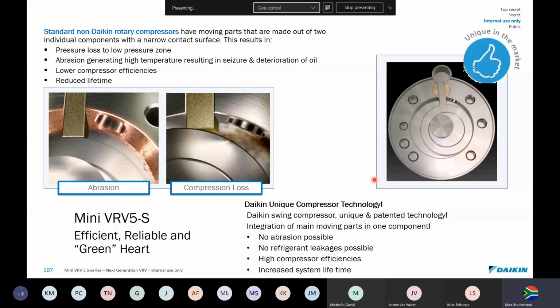So we call it the swing compressor, and it's unique. Only Daikin has it, and it's patented. You can't have any abrasion compared to this. You can't have any refrigerant leaks because this is a solid casting. Refrigerant can't leak past this surface because there is no surface for it to leak. That means because there are no internal leaks, we have high compressor efficiencies and also increased system lifetime. These compressors last a lot longer than these normal non-rotary compressors.